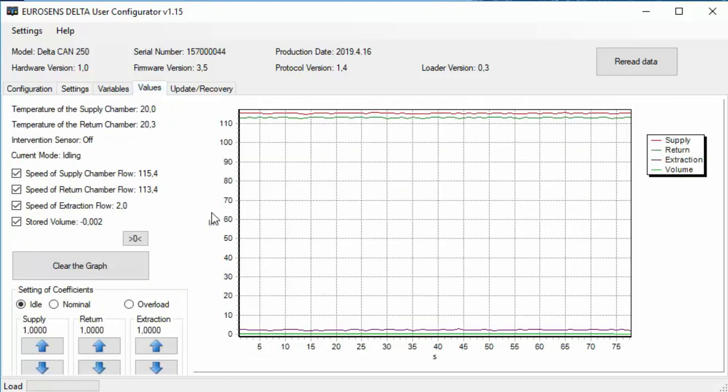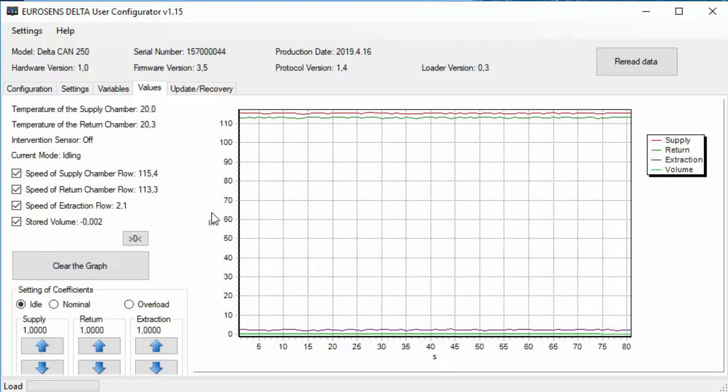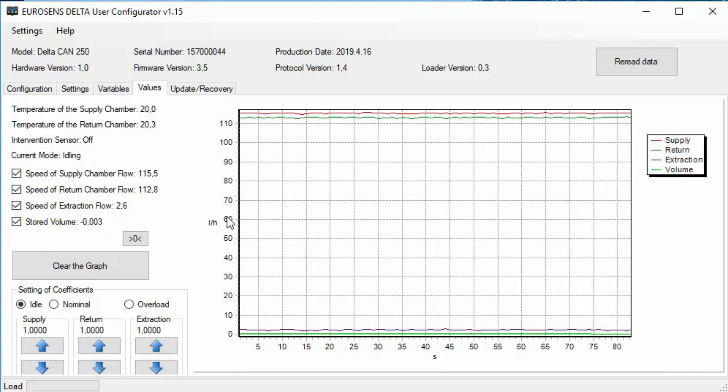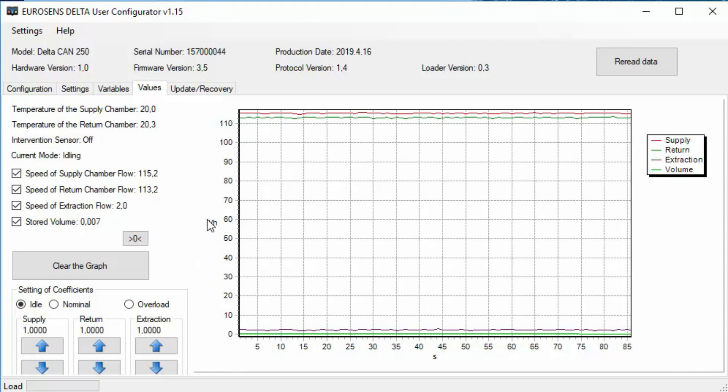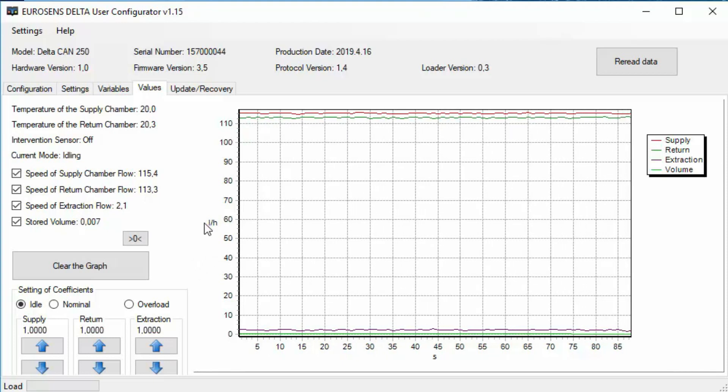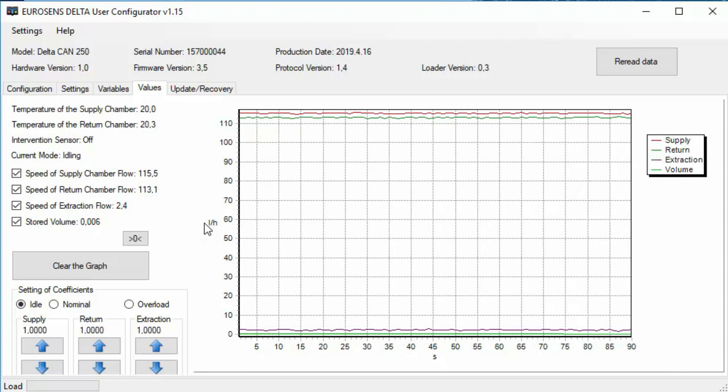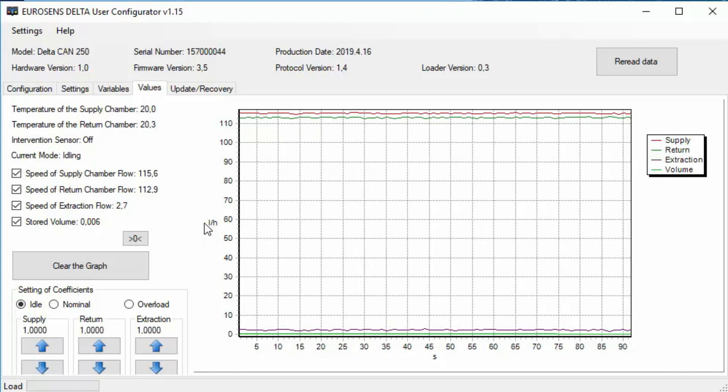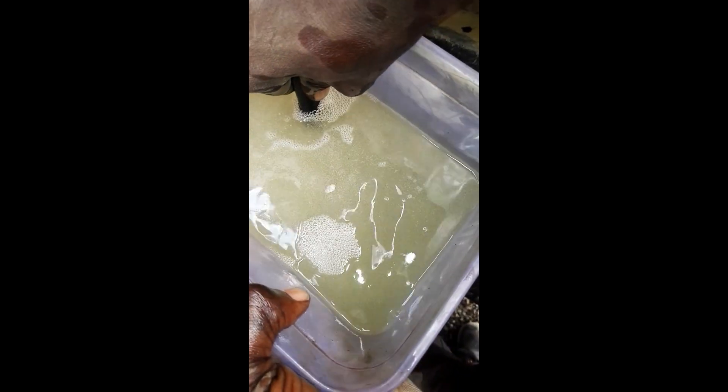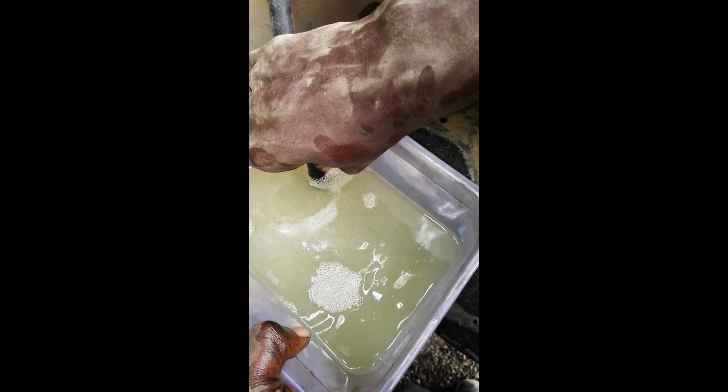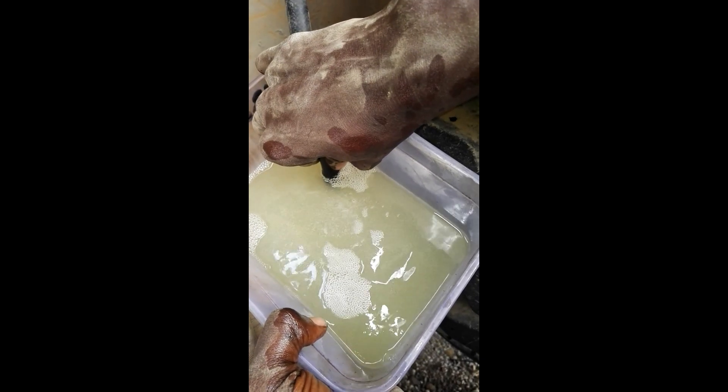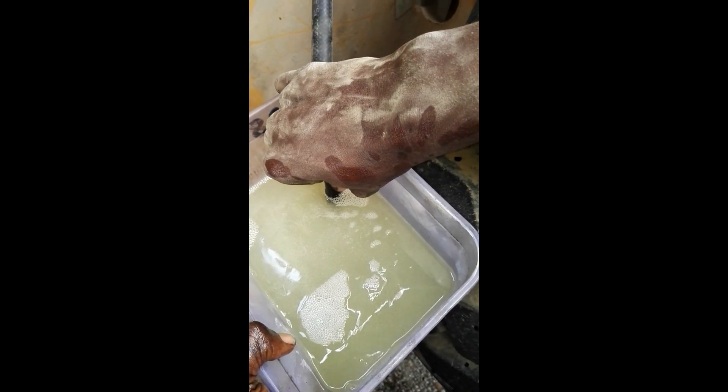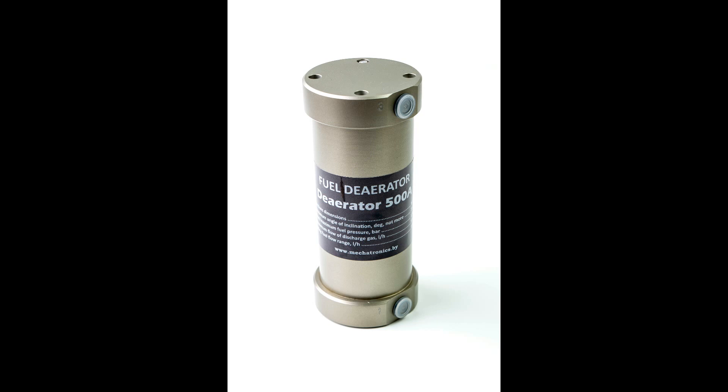The installation is successful if the resulting flow is not permanently negative. Short periods are possible when the engine's fuel consumption is negative, but in general it should be in a positive area. If the flow rate in the return line is constantly higher than the flow rate in the supply line when properly connected, check for air bubbles in the return line. In this case, you will need to install a deaerator.